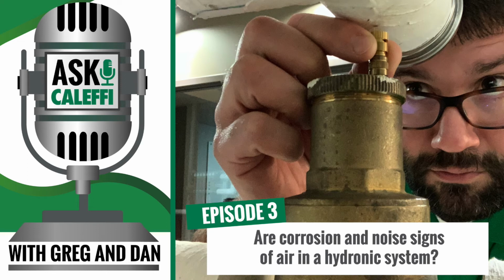Yeah, it's not uncommon, because you want your air separator at the point of no pressure change. To put the expansion tank and fill valve in below it is really common, and we see that a lot on our brass applications. But when you get to the larger steel models, you're going to see a drain at the bottom of those. Is that where you're going to want to pipe that expansion tank? Typically not. Even though it's sold as an air separator, you're looking at a larger barreled device that has a void at the bottom where debris can build up if you have a dirty system. We would hate to see someone put that on there.